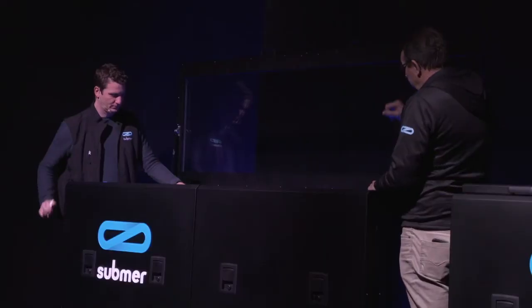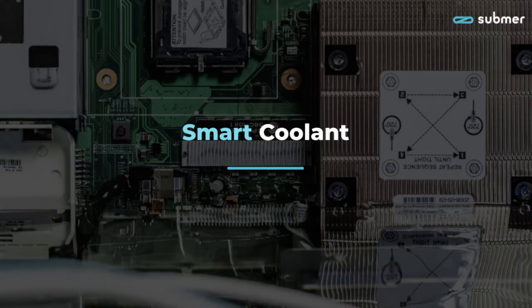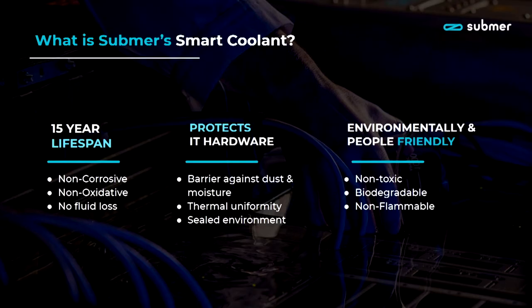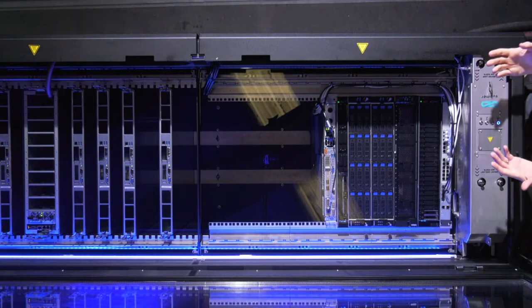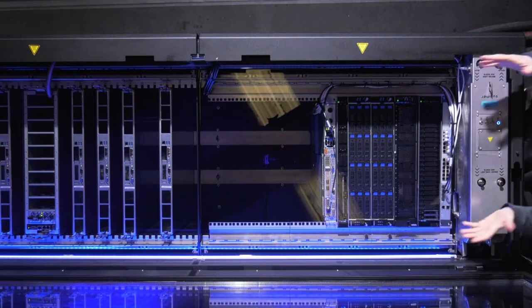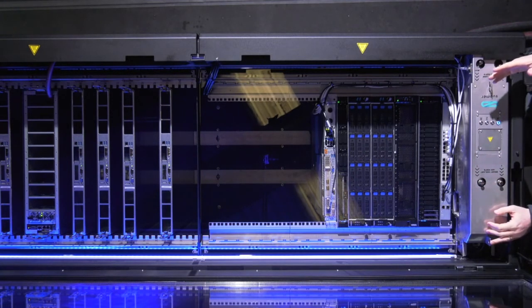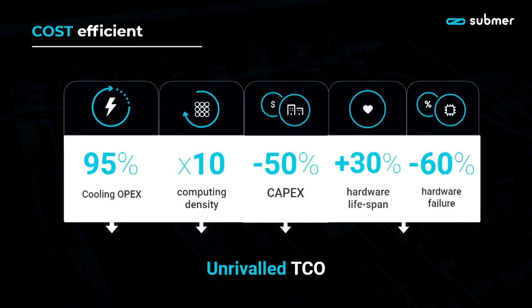in immersion. So, Daniel, what can you tell us about the fluid itself? We've designed this fluid specifically for this application. It's developed by Submer for immersion cooling, and so it has a very long lifespan, 15 years. It has the capability of capturing and transporting the heat super efficiently. It's non-toxic, it's biodegradable, it's classified as food grade, and another interesting property of the fluid is that it acts as a natural barrier to dust and particles that cause a lot of the hardware failures in data centers. Obviously this environment has no moving parts. It's completely silent because there are no moving parts, and obviously the hardware failure rate's directly connected to that. But another nice property of this liquid is it's non-flammable. And it makes things much easier from a data center security perspective.